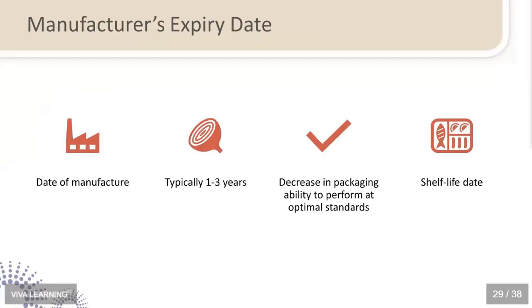So this is your manufacturer's expiration date. I said date of manufacturer, 1 to 3 years. The reason is they have done validation testing on those materials, and that has nothing to do with the sterilization process. They're just saying that these materials are going to behave and be validated to these standards up to whatever their time is. And they do both real-time testing and rapid aging testing, and that's how they come up with that time frame. That is different from shelf life dating, which we just discussed.